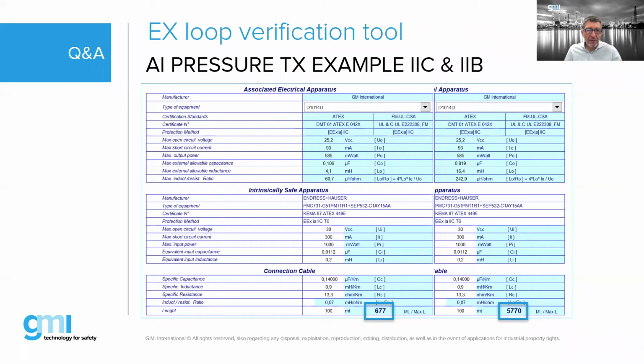You enter the data of your barrier, and the tool automatically uploads those. You enter the data of your transmitter, and the tool tells you if it is acceptable. Then of course you have to enter the data of the cable, and that depends on the quality of the cable you use. The cheaper cables typically have worse parameters. Anyhow, you can see that if I select gas group IIC, so hydrogen, my maximum distance in this application is 700 meters, which is a long distance. But if I use, what did I choose here? IIB. IIB, you can go a lot further.